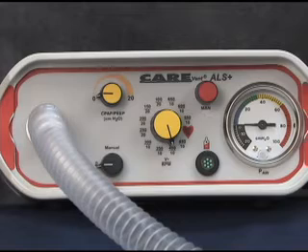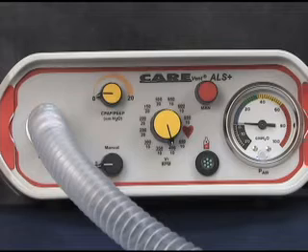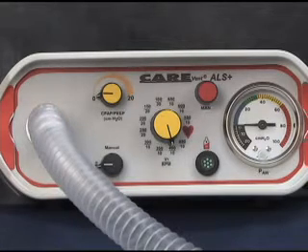In the automatic mode, should the patient commence breathing spontaneously, the CareVent ALS Plus or ALS Plus CPAP ventilators will sense the patient's inspiratory effort, and the auto shutoff circuit will stop the automatic cycling of the ventilator if the patient's spontaneous flow rate exceeds 30 liters per minute for greater than 1 second.